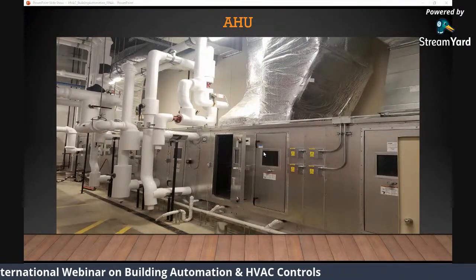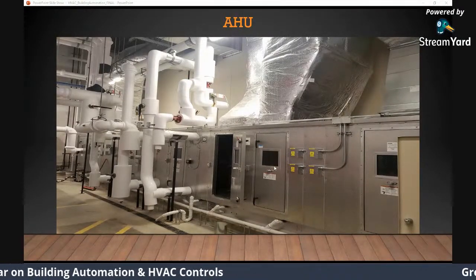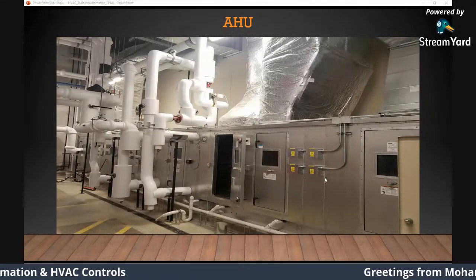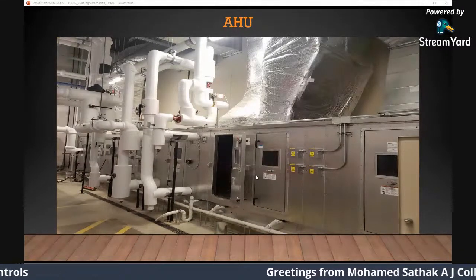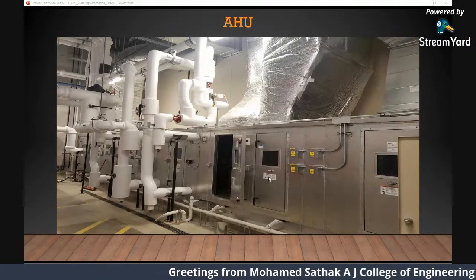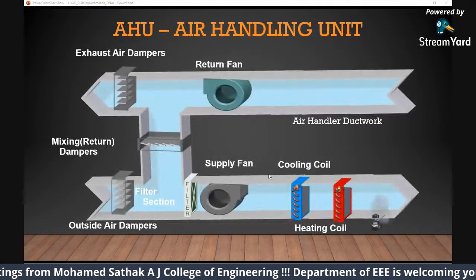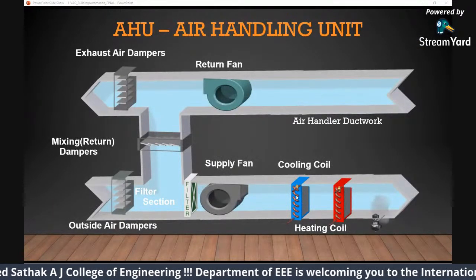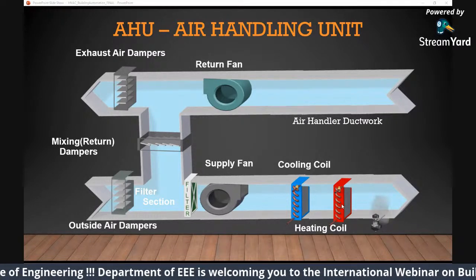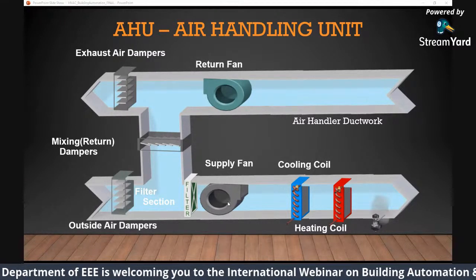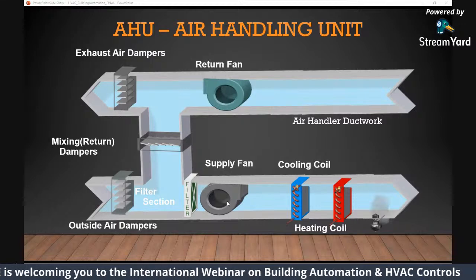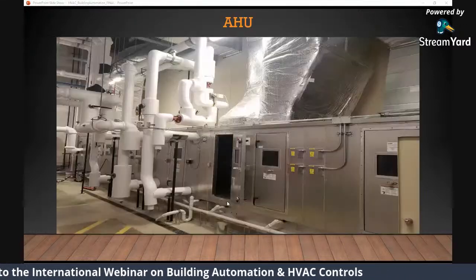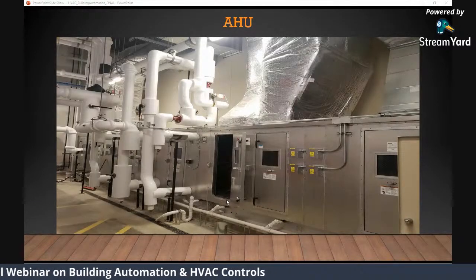That's it. All right. I cannot take pictures inside, but you can see the doors, right? One is open and the rest are closed. Each component or compartment of the AHU goes to one department. Let's say there will be one door for the cooling coil, one door for the heating coil, one door for the dampers, one door for the fan. So those are called components or compartments of the AHU. If you get inside, that's how big your coil is.